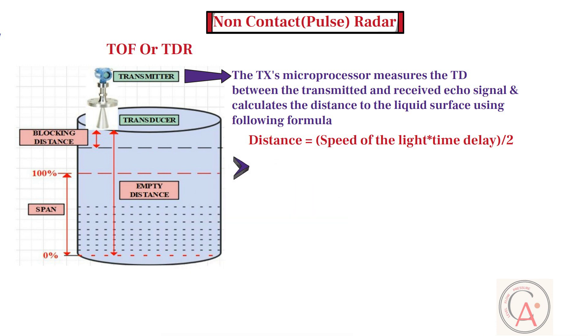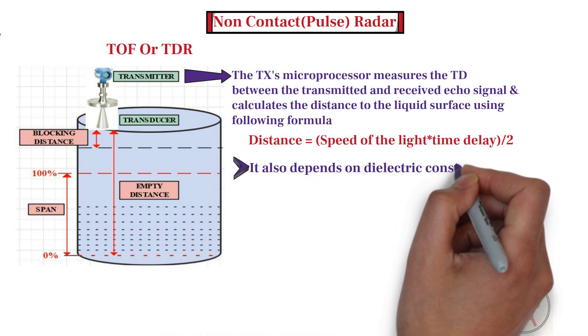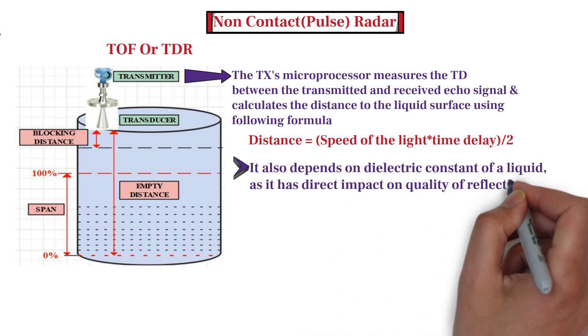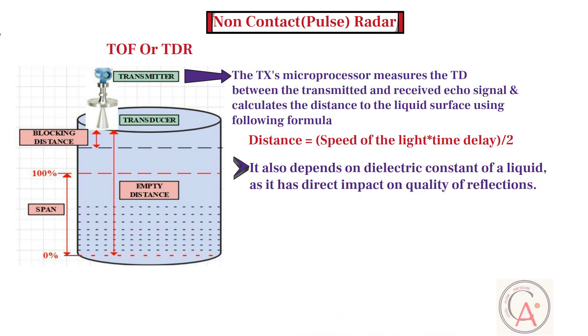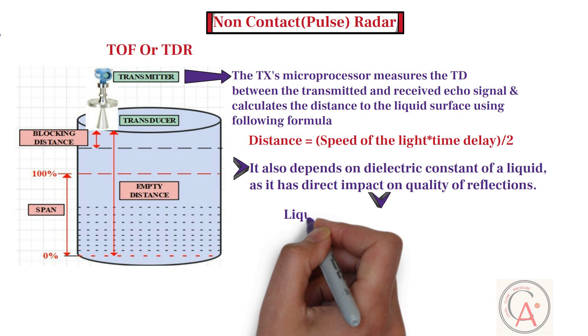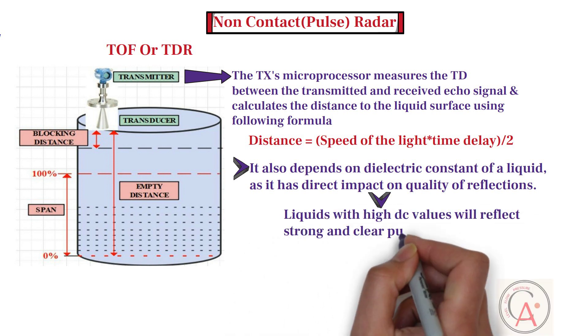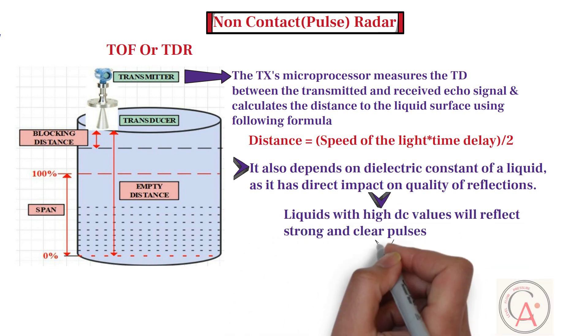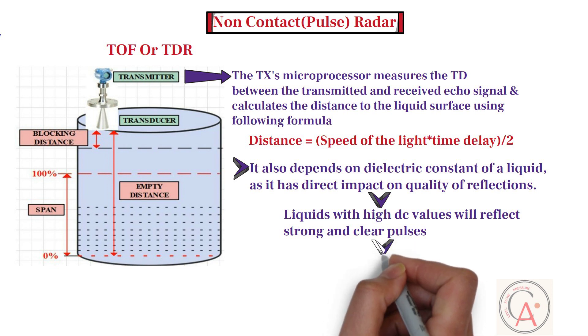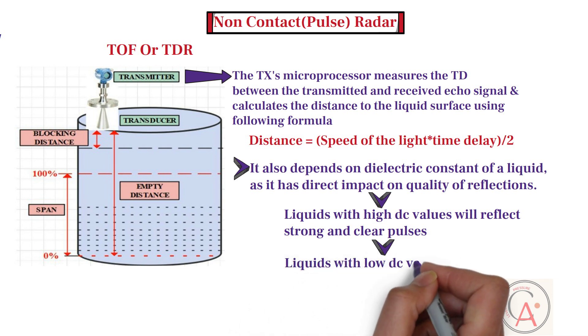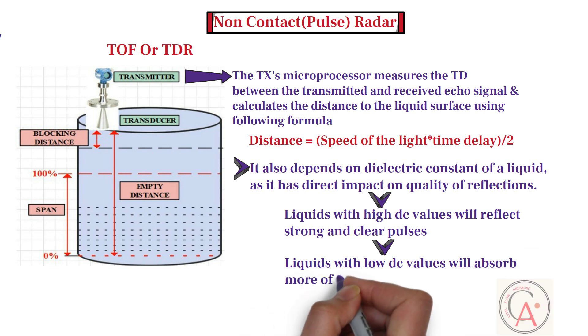Radar level measurement is highly dependent on the dielectric constant of a liquid, as it has a direct impact on the quality of reflections. Liquids with high dielectric constant values will reflect strong and clear pulses. On the flip side, liquids with low dielectric constant values will absorb more of the pulse, reflecting less and reducing accurate readings.